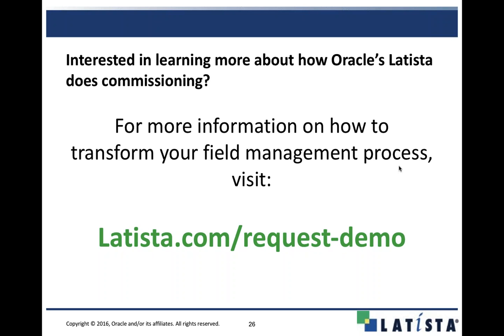Josh, the first question is: if someone were to go through with utilizing Latista on their next project, from a user perspective, what does it take to get things set up and working? It's all about planning. The commissioning plan needs to be drilled down, and once we're breaking ground, the commissioning plan has to be treated just as seriously as getting construction complete. It takes issued-for-construction drawings, specifications, and approved submittals in order to create those quality control commissioning checklists and templates.